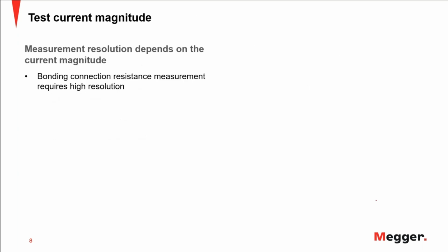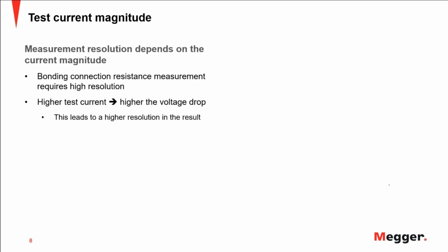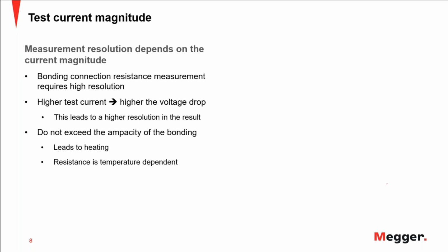So the next thing to cover is the current magnitude when we want to measure low resistance. What is the best current to use for the measurement? Basically, the magnitude of the current is going to give you more resolution or lower resolution in the measurement. Meaning that higher current will give you higher resolution, a much better result.